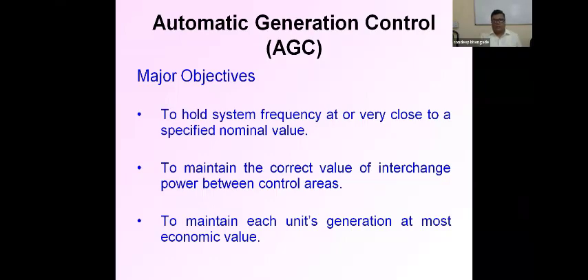Okay. Now, what are the major objectives of automatic generation control? First is to hold system frequency at or very close to a specified nominal value. When you look at the output of the grid or the power system, the output is an indication of some error, and this error occurs because of the difference between the power demand in a system and the generation. So the difference between generation and the demand gives some error, or we call it a deviation in the system frequency. If AGC maintains the system frequency close to a specified nominal value, it minimizes the error. Okay, this is the first objective of AGC.